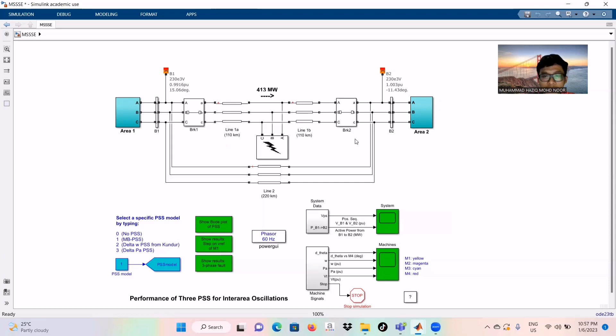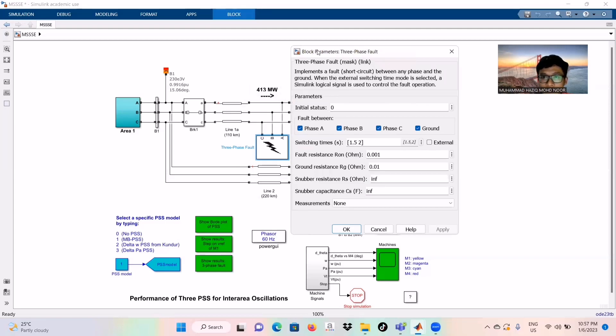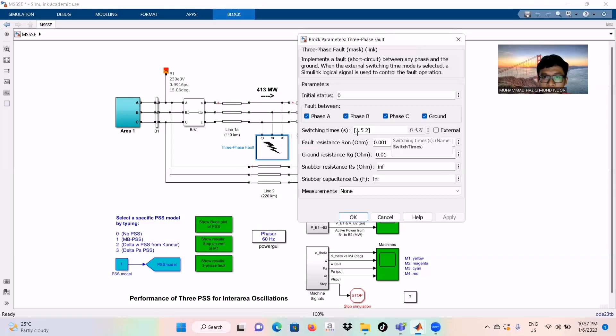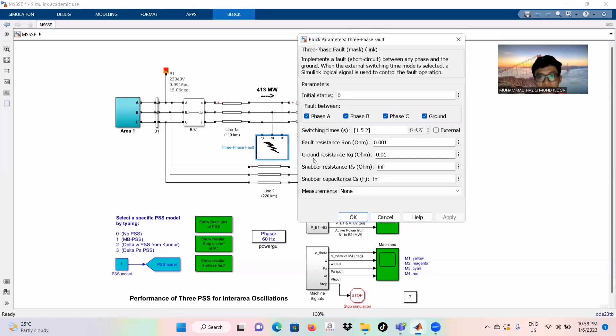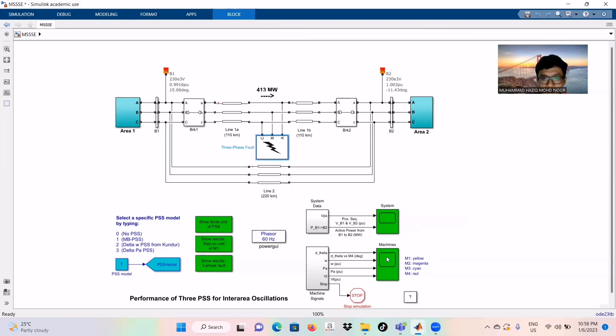For the temporary bolted 3-phase fault, we use the component from SimScape in MATLAB Simulink named '3-Phase Fault'. We wire it up between bus 1 and bus 2. We click on the block for the 3-phase fault and set the switching time to 1.5 and 2 seconds. We will observe the changes in simulation time from 1.5 to 2 seconds, where there will occur steady state, dynamic stability which is unstable, then stable.